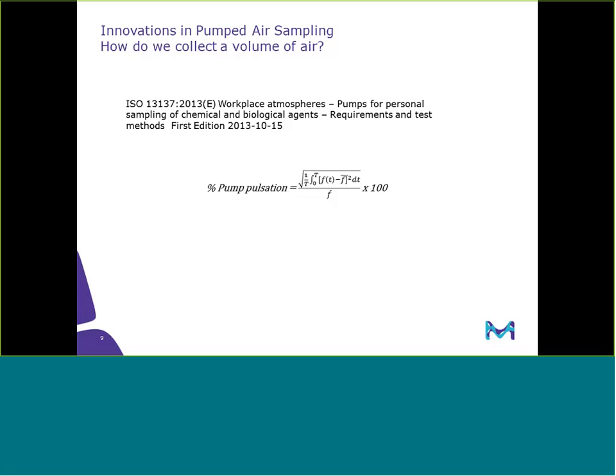But ISO also has a specification that pumps should not exceed a 10% value for pulsation of the flow rate, and this is under certain specified conditions. I would refer everybody to take a look at the ISO method and see how they determine this as far as the conditions go. But we'll proceed from now.